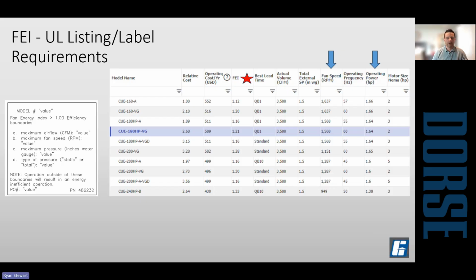And I want to share this example here. This is out of CAPS, and you'll see this is 3,500 CFM at a 1.5 inch static pressure. The like wheel sizes, the 160s, 180s, 200s, those are identical wheels. When you look at this, everything appears to be equal, even brake horsepower and RPM for the like fans. But if you take a closer look at the FEI, you can see that it varies. For comparison, a fan that's at a 1.21 is 21% more efficient than the code minimum baseline fan. And in this case, the reason that fan's the most efficient, at least for that size, is because of the EC motor. On the left there, I've given you an example of what the UL label says. As a manufacturer shipping fans into states that have the requirement, they have to label the fan to show what the performance is that meets the minimum 1.0 FEI requirement.